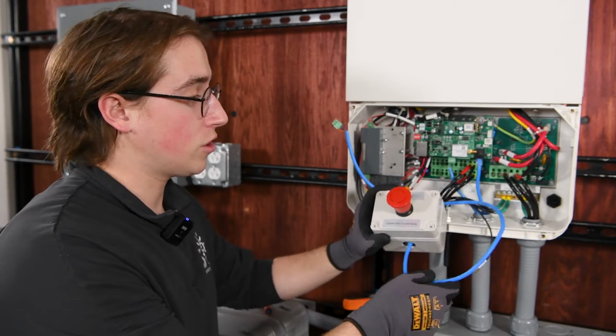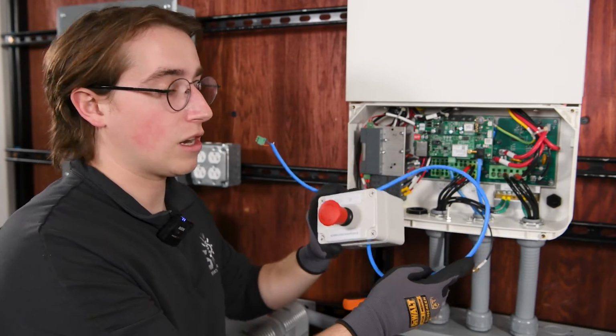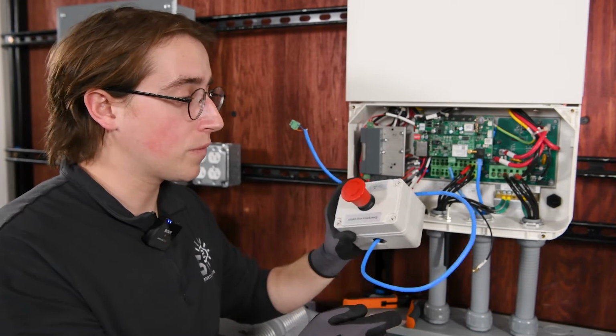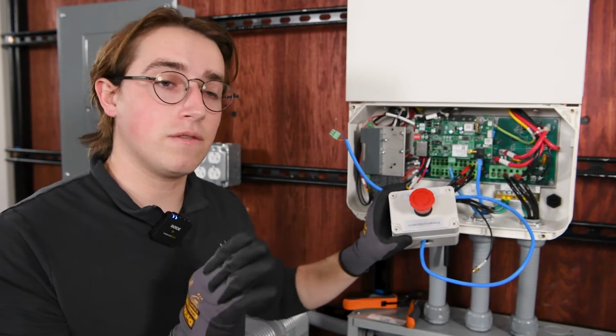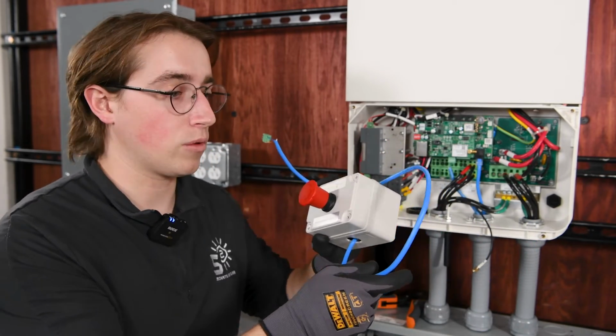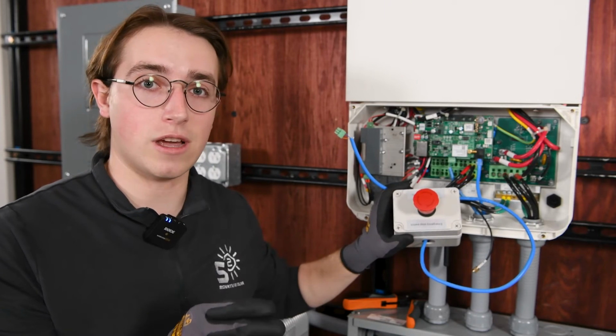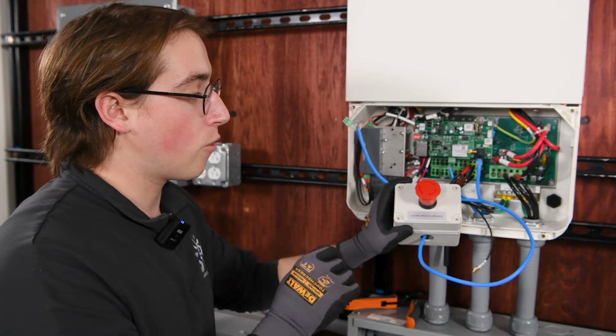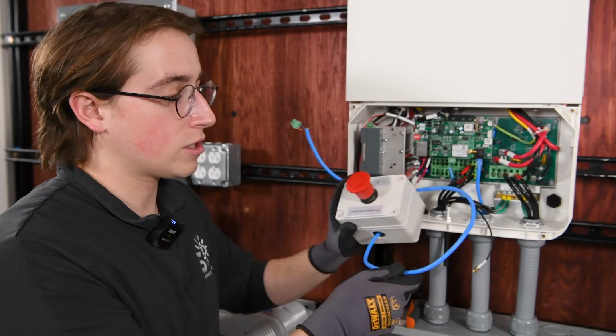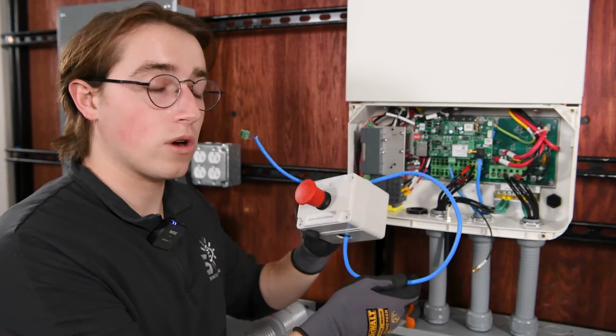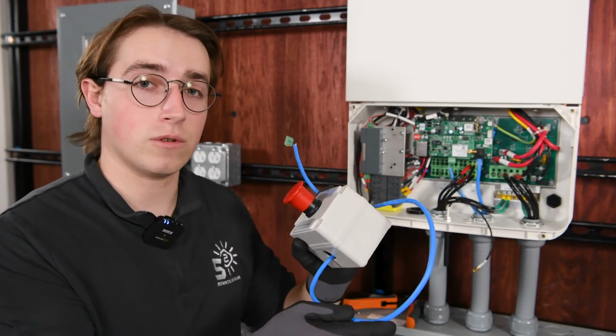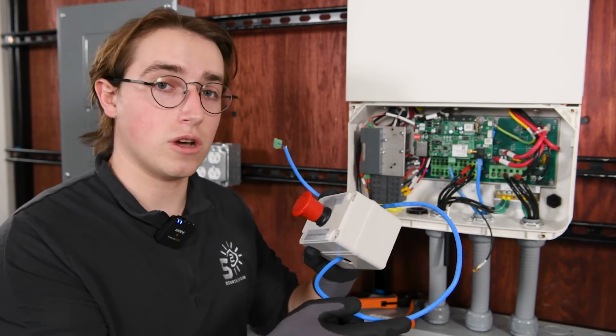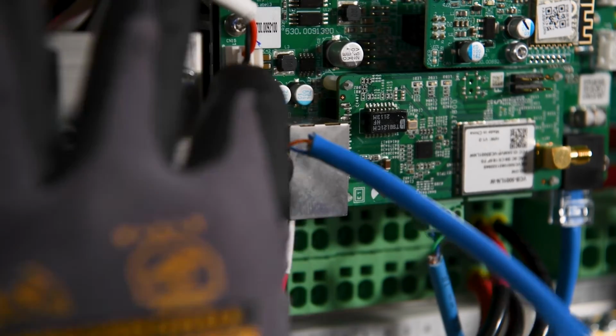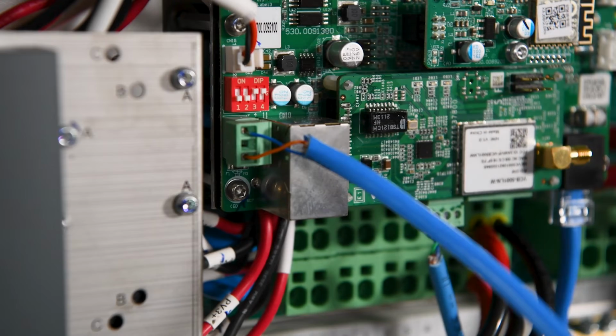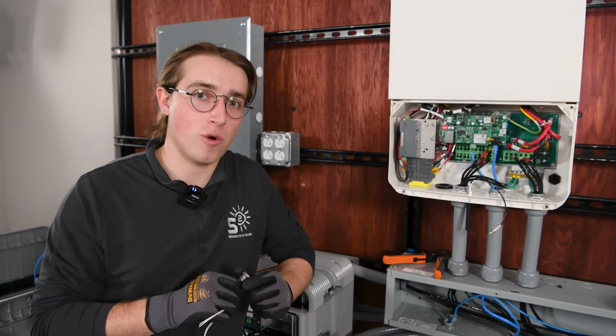For this test and this commissioning video, we are using just a standard Cat5 or Cat6 Ethernet cable, but keep in mind, depending on the environment that you're running your communication cable through is going to determine the wire type that you actually need for this communication setup. For us, again, standard Cat5 or Cat6 will work, but for you, that may differ. So ensure that you're working with your local installers to make sure you have the correct wire type to carry this signal. A noteworthy mention is the Darkstart feature that Growatt offers.